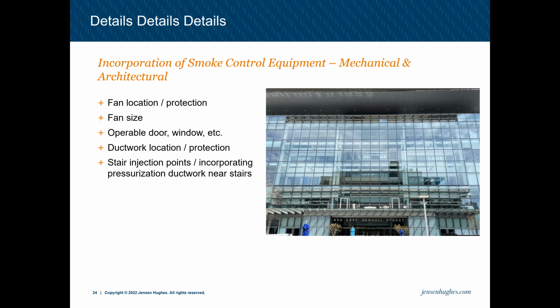Other big mechanical items to consider, as Tony talked about, is where you're injecting air into a stair. If you're going to try and inject at the lowest level, which makes it easiest to balance and will make commissioning easier, but obviously takes up space to get ductwork to the first floor or basement levels of a building, or instead you're going to try to inject from a very high level and just hope that's sufficient to pressurize the stair or hoistway.